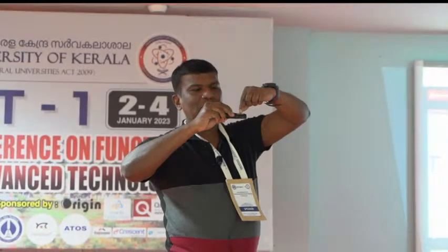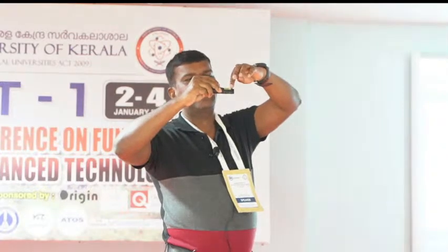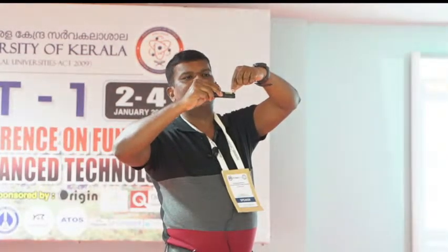In that way, whenever the electrostatic force happens, it will not affect your PFM measurements, because the first force that will attract the sample is the electrostatic force if your sample is conductive in nature. And you need to get rid of that. To get rid of that, your force has to be higher than the electrostatic force. So if you put your cantilever laser at the end of the cantilever, it will not show you the actual PFM signal.